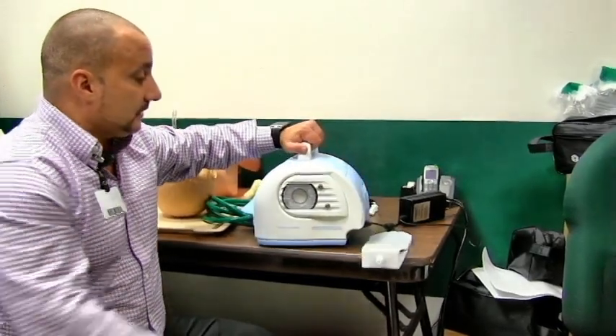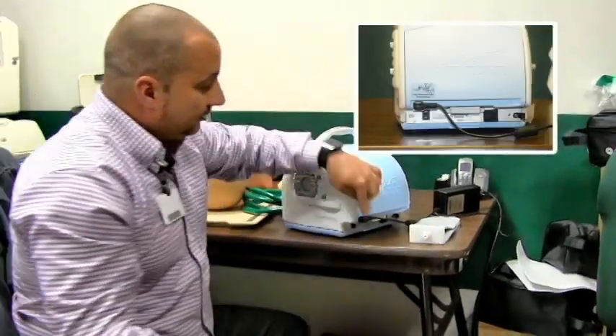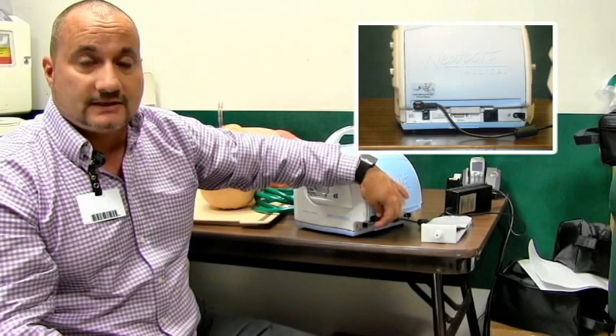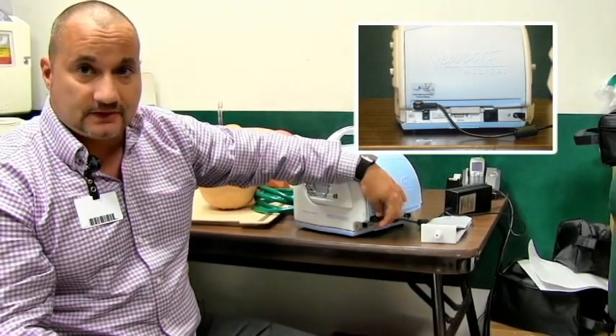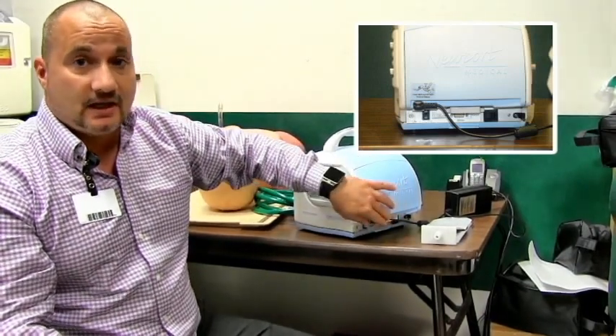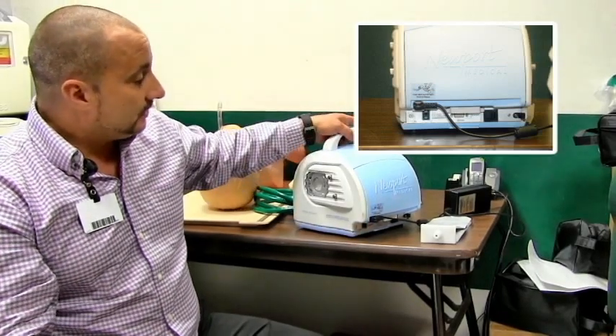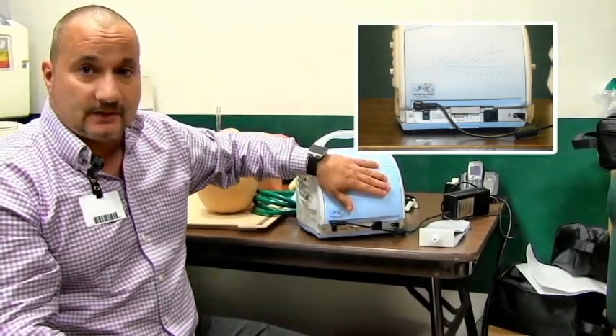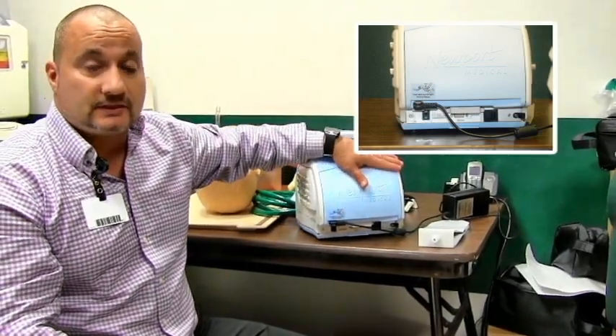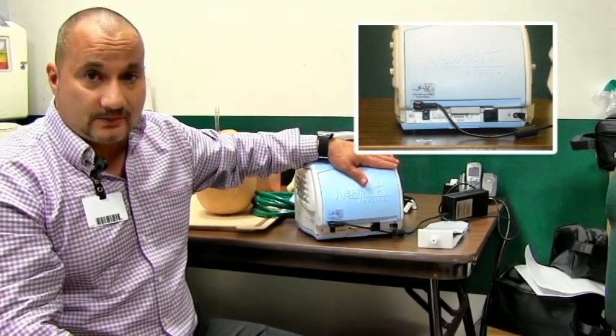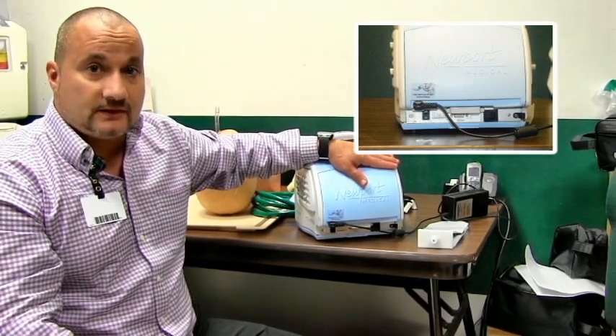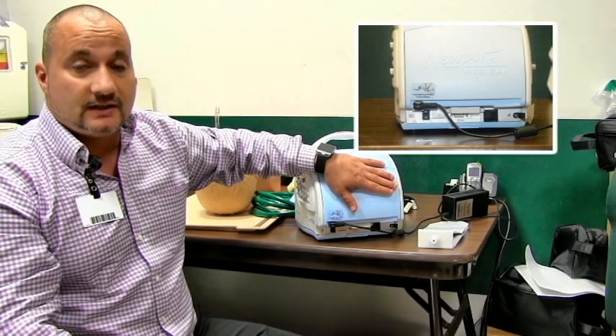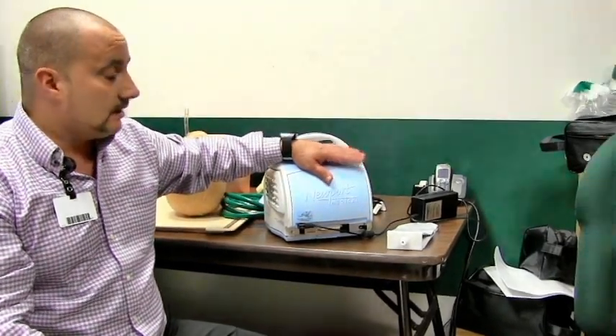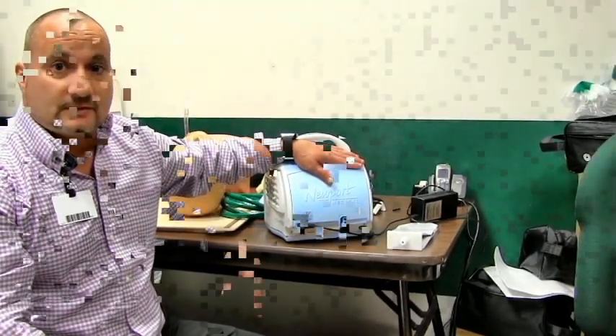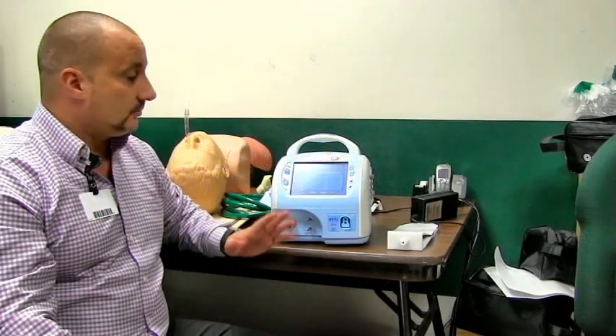On the back of the unit here, you'll see where the plug-in goes. When you discharge the plug to take it out, it's just simply a pinch. When you put it back in, it's the same thing, and it will feed back into the unit. Behind the unit too is the battery pack itself. The battery pack will stay charged. We'll get about 10 hours of battery life with a fully functioning ventilator with most of the things running on the ventilator. But again, we want to keep it plugged in as often as possible. So the machine is on now.